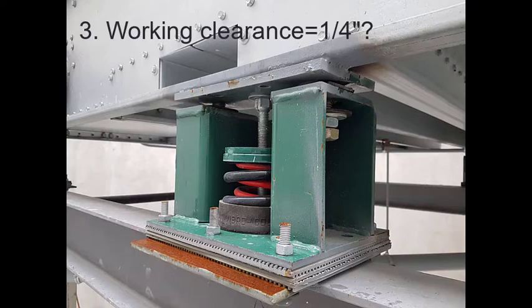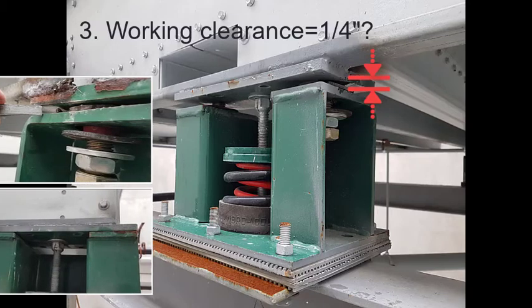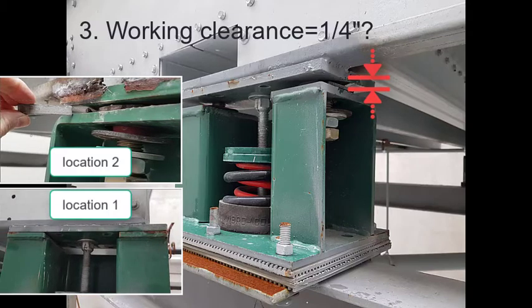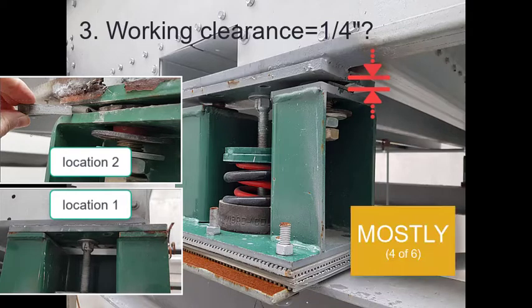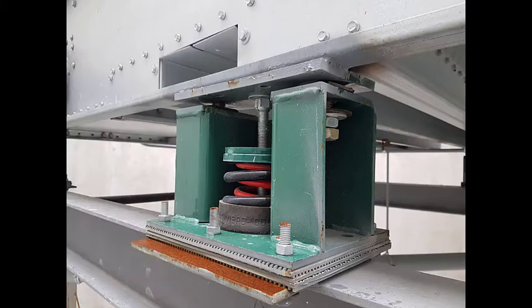Is the working clearance 1/4 inch? Well, here at location 5 it's okay, but we found that locations 1 and 2 have less clearance than shown on the datasheet and locations 3 and 4 have more. As explained in the previous question, this one goes in the mostly okay category since most of the isolators have the clearance, but the contractor may need to readjust the springs if any noise problems arise.